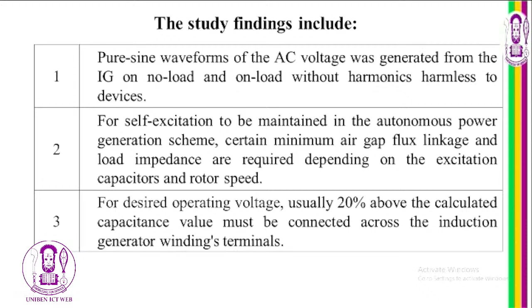For excitation to be maintained, a certain minimum air gap flux linkage and load impedance are required, depending on the capacitor and the rotor speed. For the desired operating voltage, a capacitance value usually 20% above the calculated amount must be connected across the induction generator winding.